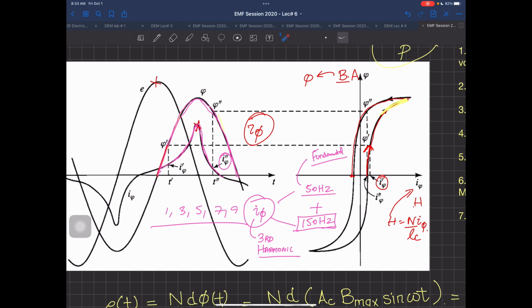There is also a problem of harmonics in machines, and this arises because of the material property. If the material's property has saturation, and you have designed into its saturation region, then you are going to have harmonics over there. If you designed the BH curve leaving it at this point and cutting it off here, saturation doesn't come in, or it comes in only very little.